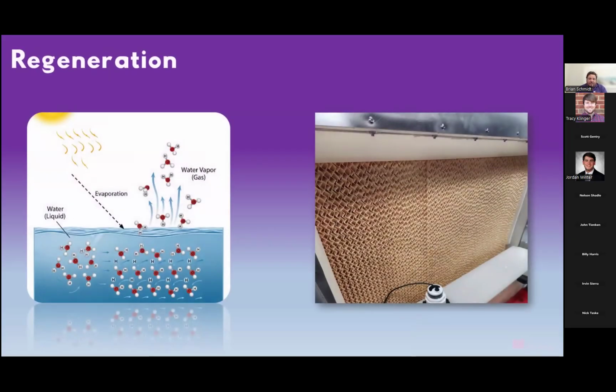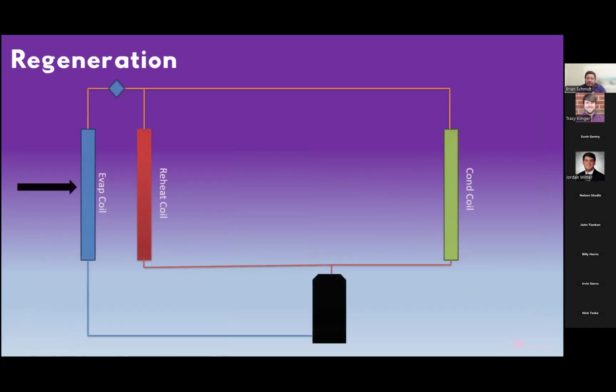Speaking of regeneration, again, we need heat to evaporate the moisture out of this pad. Again, it's the pad that you see on the right. It's a little bit bigger than the absorber pad. This is called the desorber pad, and it's on the other side of the unit. But essentially, we are using heat to evaporate moisture out of this solution. Diluted desiccant flows down from the top to the bottom, and we are reconcentrating it as it flows down by allowing that heat to evaporate moisture out of the solution. How do we do that?